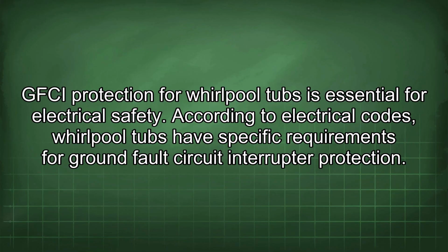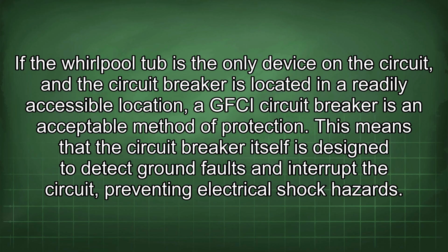GFCI protection for Whirlpool tubs is essential for electrical safety. According to electrical codes, Whirlpool tubs have specific requirements for ground fault circuit interrupter protection. If the Whirlpool tub is the only device on the circuit and the circuit breaker is located in a readily accessible location, a GFCI circuit breaker is an acceptable method of protection.